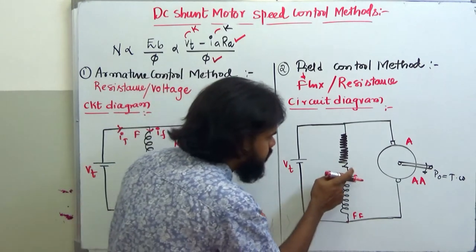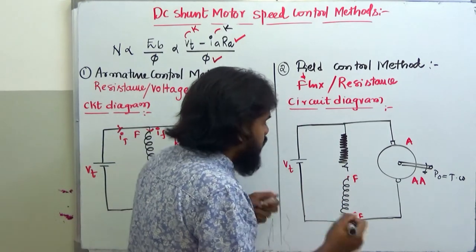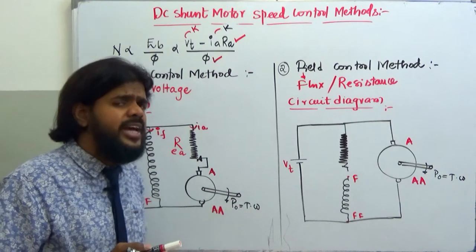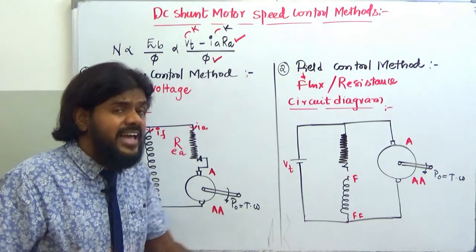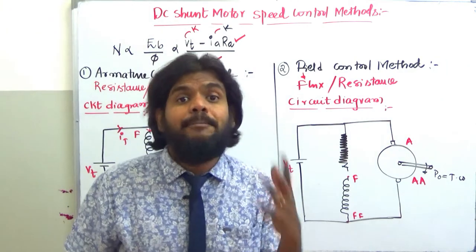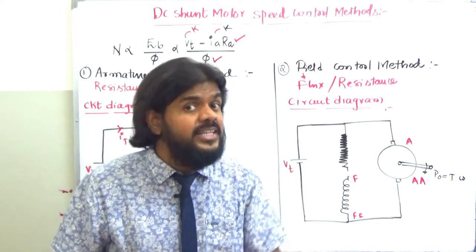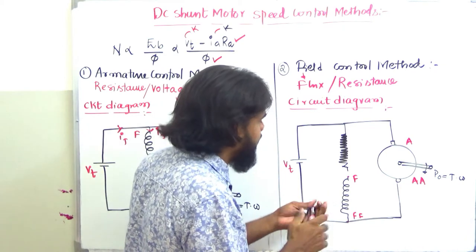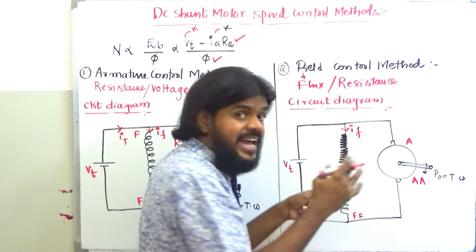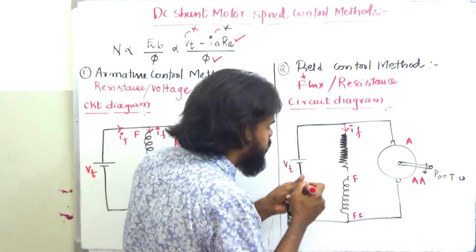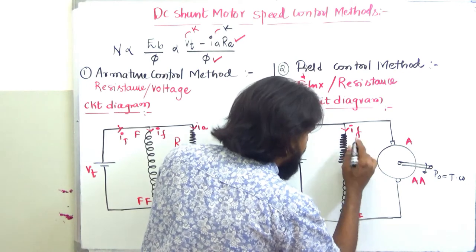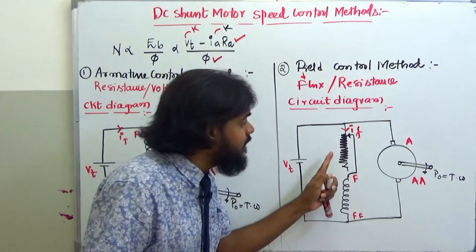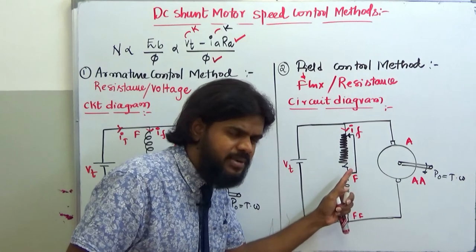The second method is based entirely on variation of flux. You can change the flux by changing the field current — the current flowing through the field winding. To change this current, we connect an external resistance in series with the field winding, so that we can vary the field current and thereby change the flux.